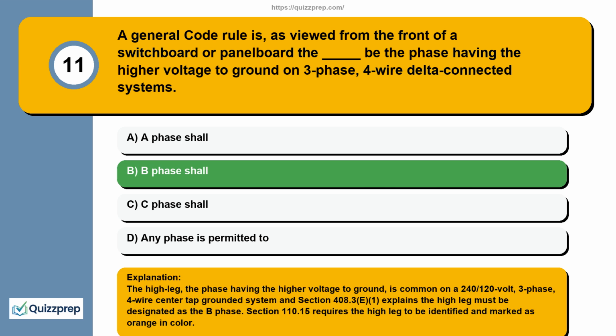The high leg, the phase having the higher voltage to ground, is common on a 240/120-volt, 3-phase, 4-wire center tap grounded system, and Section 408.3(E)(1) explains the high leg must be designated as the B phase. Section 110.15 requires the high leg to be identified and marked as orange in color.